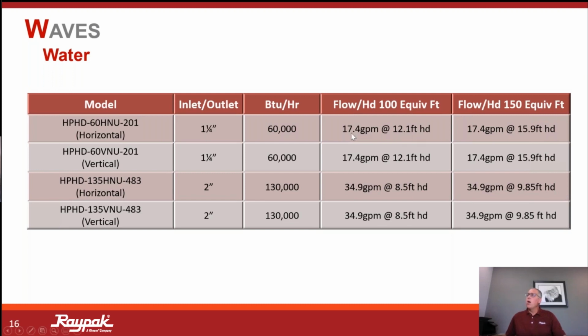On the water side, we are looking at some fairly high flow rates. You might notice that for a 60,000 BTU unit, we have some very proportionally high flow rates compared to our fossil fuel counterparts. The reason we do that is that we want these higher flow rates to run a very narrow temperature rise across that appliance. Again, that's going back to the basics in the math. If our BTUs out are constant and we decrease the flow rate, more temperature or more BTUs can get on that bus. If I increase the flow rate, I'm going to have a narrower temperature rise because not as many passengers can get on that bus. So we are talking about a multi-path system between the tank and the unit itself. So a multi-path design is something we're going to talk about.